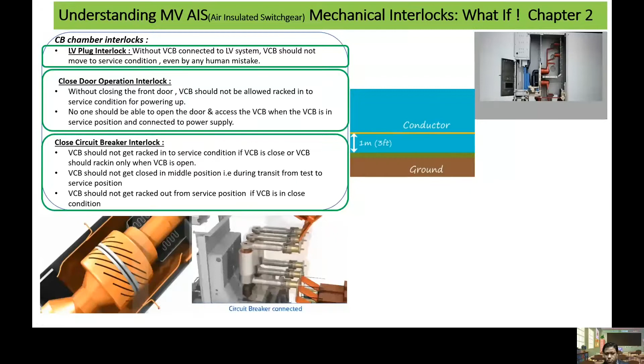Now let us understand what happens if the interlock is not present. Here you can see the circuit breaker is engaged with the cubicle or the fixed part of the circuit with the help of this contact, and then the circuit is getting completed once you close the circuit breaker or the vacuum interrupter present in between both the circuits. Now if a person is allowed to rack out the breaker, this portion of the contact will come out, and then the air between these two conductors will get ionized, and then there will be flashover which will create damage in the circuit breaker. And if this flashover continues, it will convert into an internal arc which will impact the person who is operating the circuit breaker, because the person operating the circuit breaker will be connected to the ground.